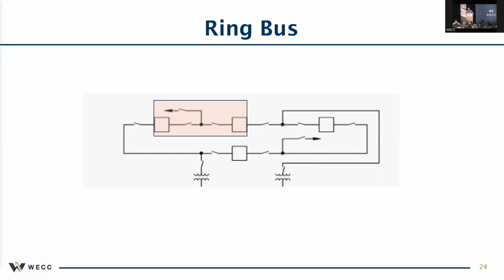Now, your methodology can determine when you look at those 2 breakers, whether you're going to say, I'm going to assume the most limiting of those breakers or the single breaker, or you can say, hey, these breakers together handle that flow, and I'm assuming 50-50 flow, 60-40 flow. That's part of your methodology, how you want to address those 2 breakers for impacting that rating. You have that control, but not considering those breakers.